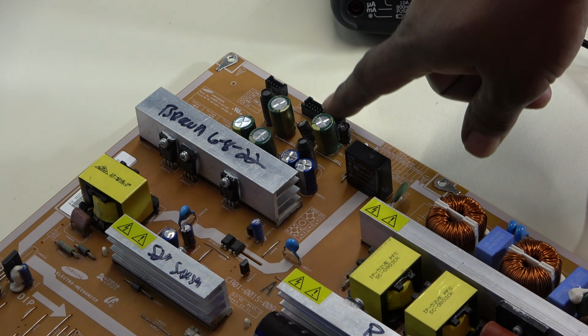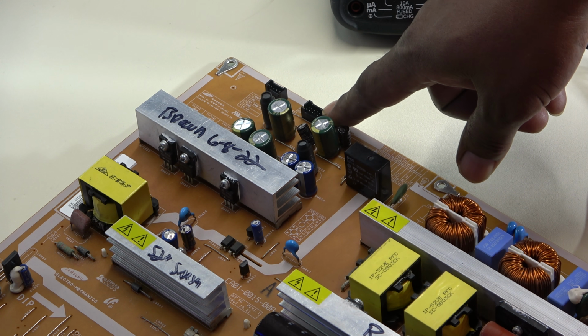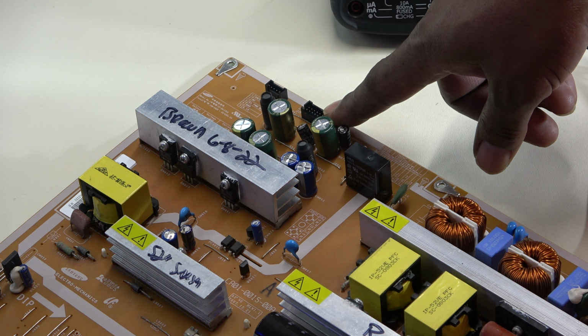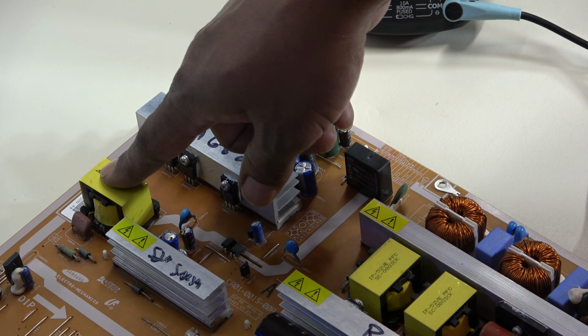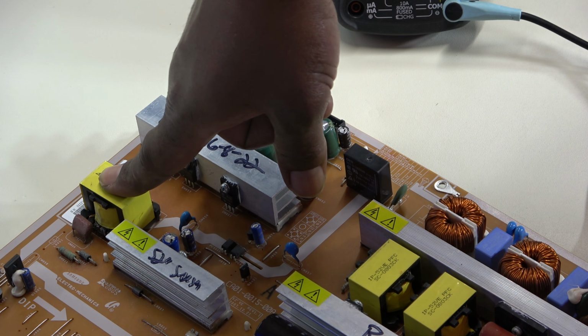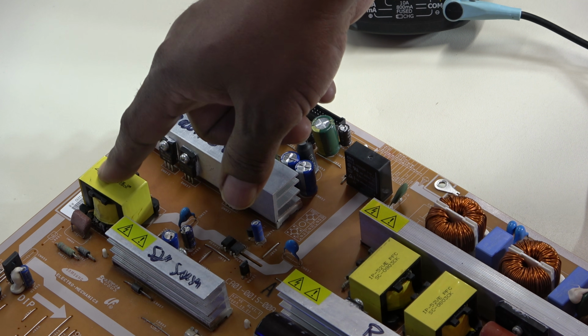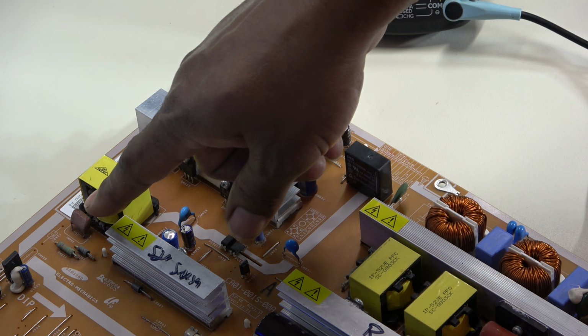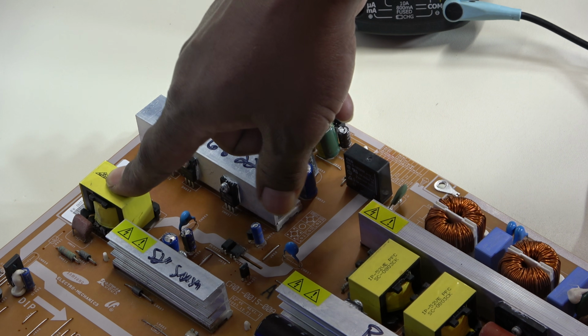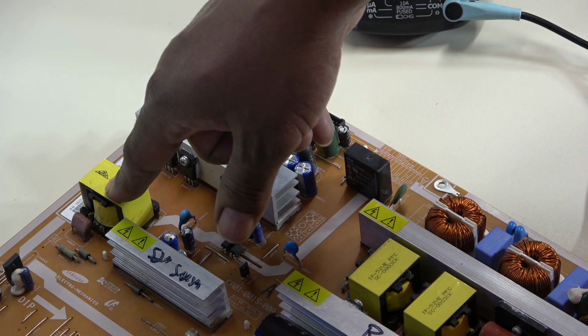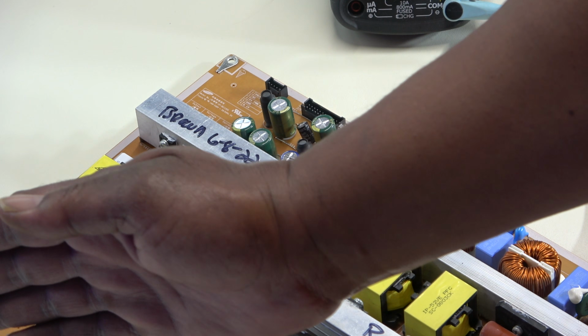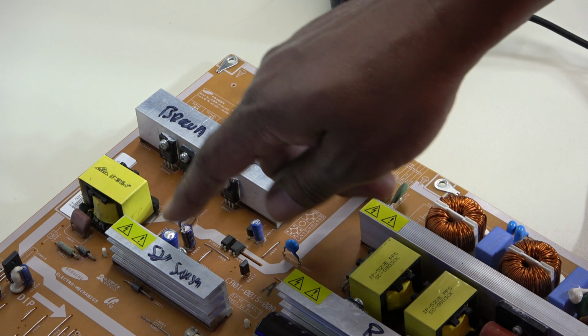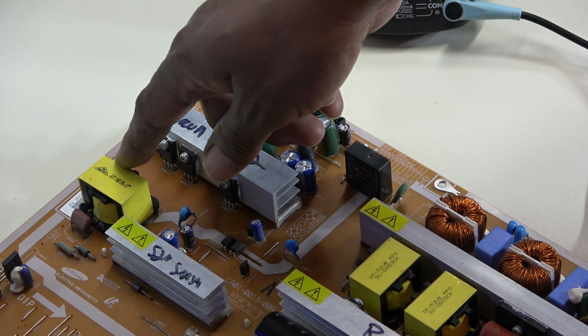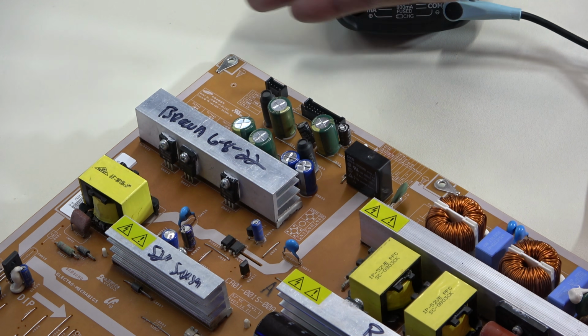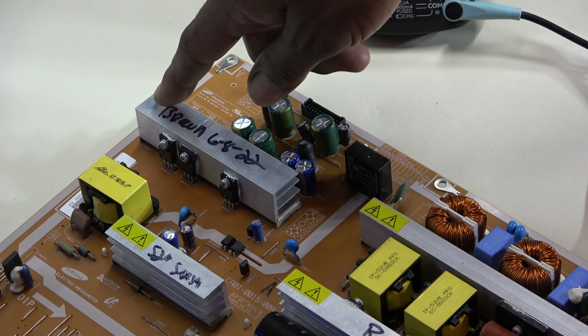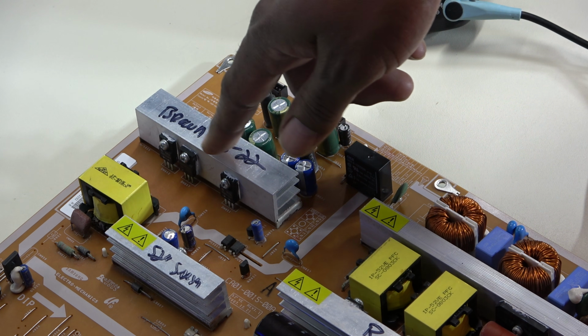If we go to our plug, where our startup voltage is at, it's missing. Most likely this transformer is where that voltage is coming from. What happens is there's DC voltage on the high side, going through this transformer on these windings, producing voltage on the secondary side, which is then rectified by these diodes.